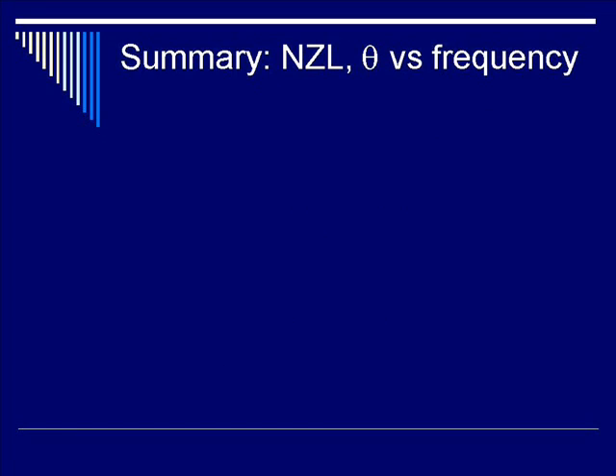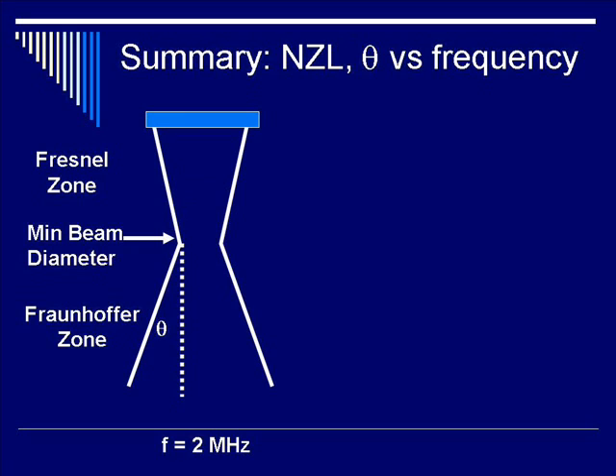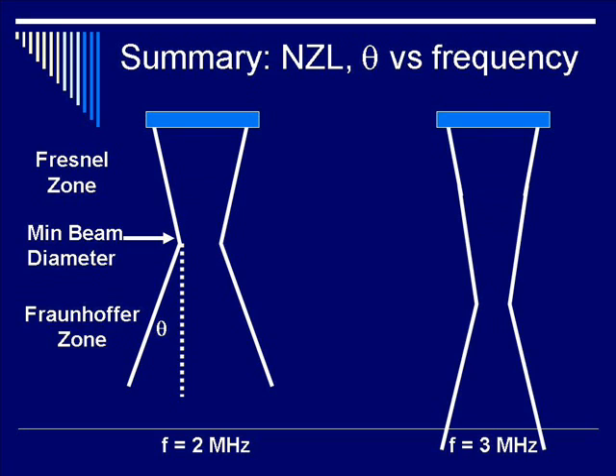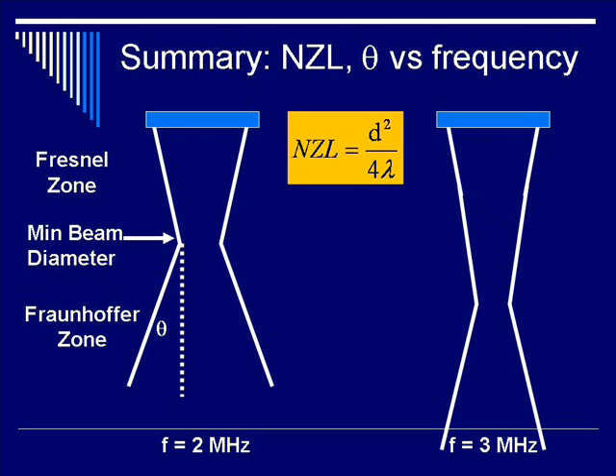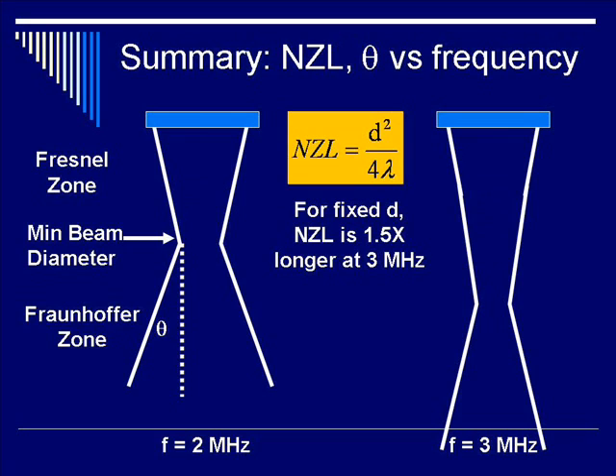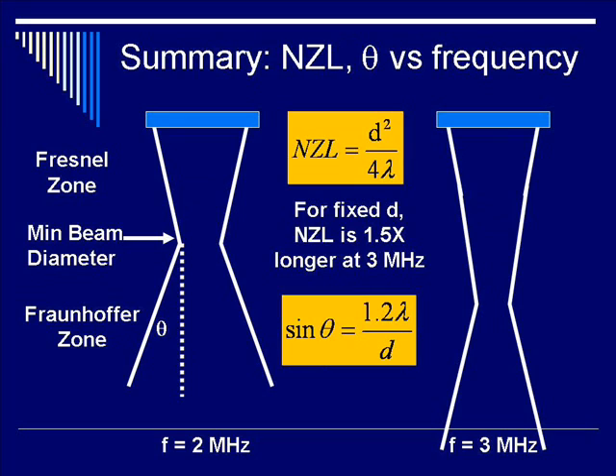Let's summarize the dependence of NZL on frequency and beam diameter. At 2 MHz there is a certain beam profile; increasing frequency to 3 MHz causes NZL to increase. Since NZL is inversely proportional to lambda, and higher frequency means smaller lambda, NZL increases by 1.5 times at 3 MHz compared to 2 MHz. For beam divergence, sine theta is proportional to lambda and inversely proportional to D; so increasing frequency decreases lambda, therefore sine theta and theta both decrease.